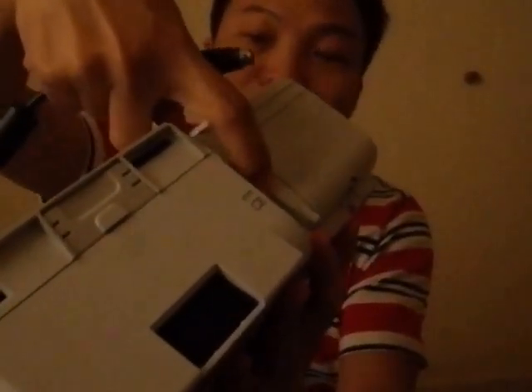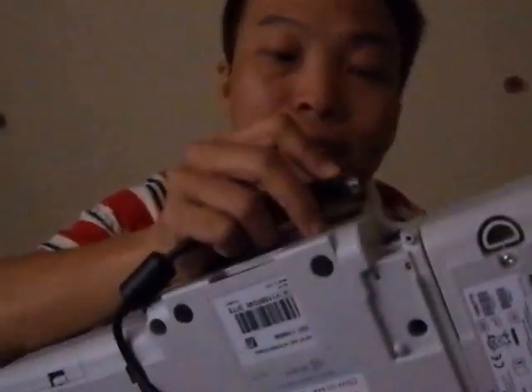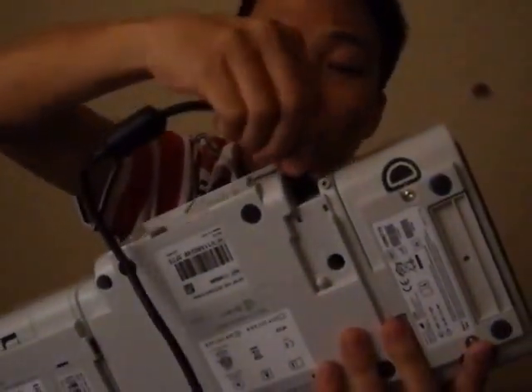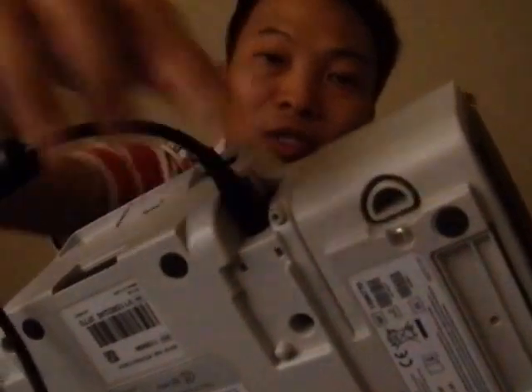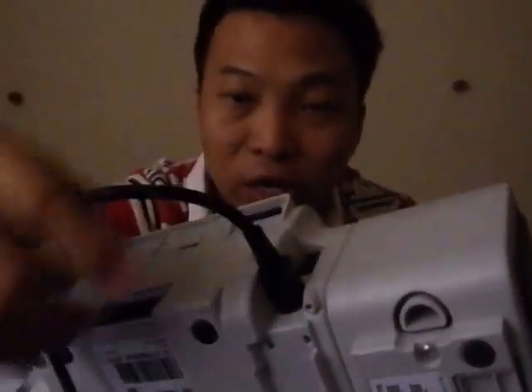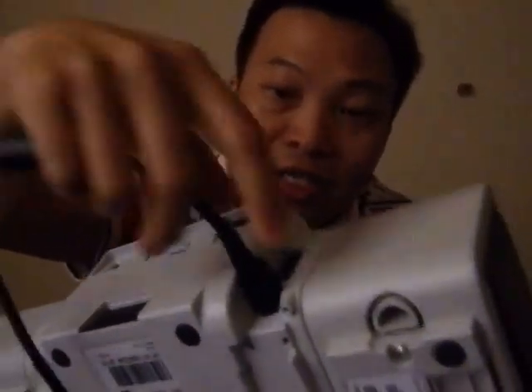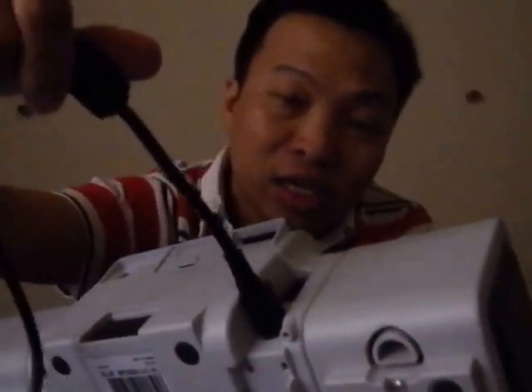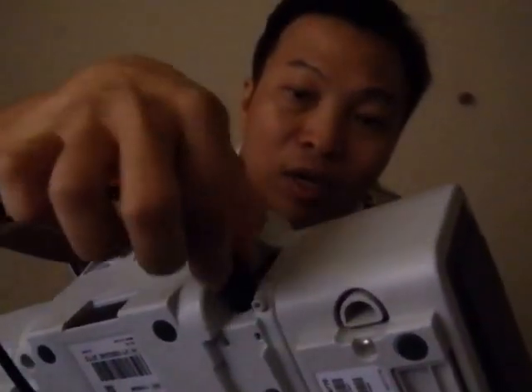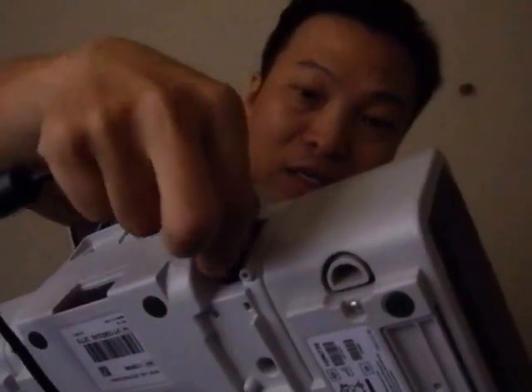There's a port here. On the side of the port there's a white dot. I think it's hard to see from the camera. You need to identify the white dot, and then you also need to identify another dot here to connect the AC power cord. When you push in, you can hear a clicking sound. Once it is connected, you can't pull it out like this. It has a locking mechanism to prevent accidental disconnection. You can only disconnect the cable by moving this part here. When you want to disconnect the cable, there's a moving part.